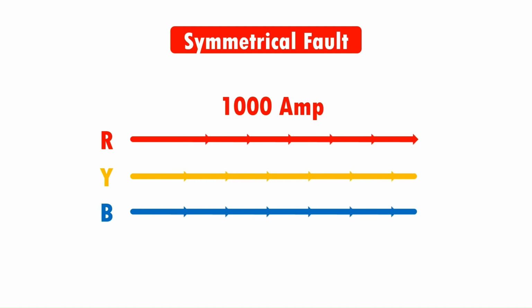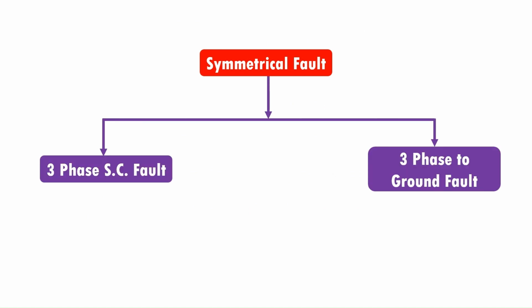Symmetrical faults are the most severe type of faults due to the flow of massive current. The occurrence of the fault is very rare. They account for a very small percentage of all power system faults. They mainly occur at the terminals of the generators. The symmetrical fault is subcategorized into three-phase short circuit fault and three-phase line to ground fault.